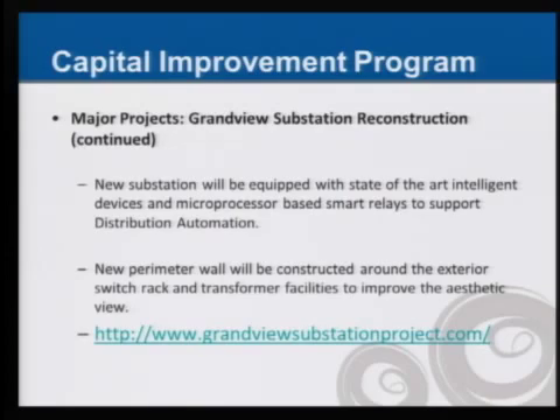The new substation, as part of this project, will have state-of-the-art protection relays and equipment, which will support a distribution automation program. In addition, aesthetically, currently outside the switchgear rack there's a fence around it that you can see inside the substation. As part of the project, we're going to put a perimeter wall covering all the transformers and switchgears within the yard.